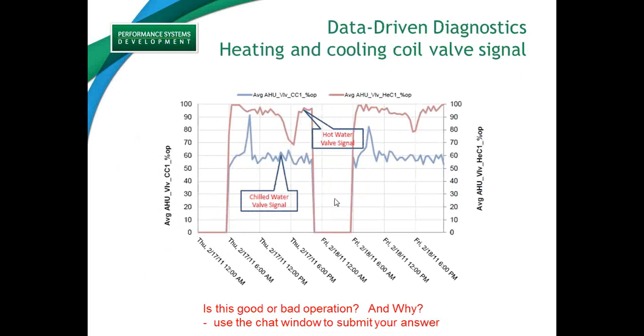So if you're trying to understand, is it good or bad? First of all, we have the valve looks like it's completely closed at nighttime from about 12 at night to 6 in the morning. That's probably good, right? We don't need heating or cooling at nighttime typically.